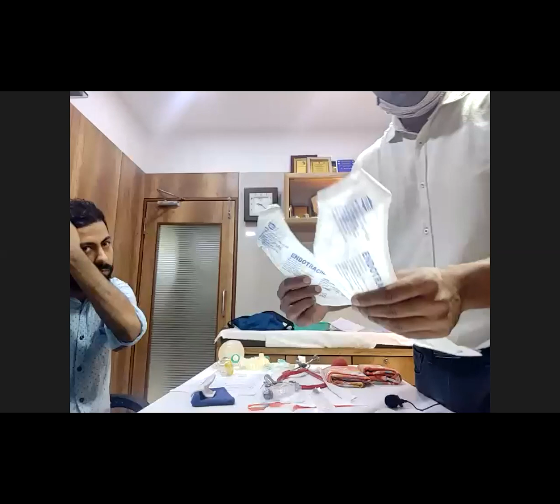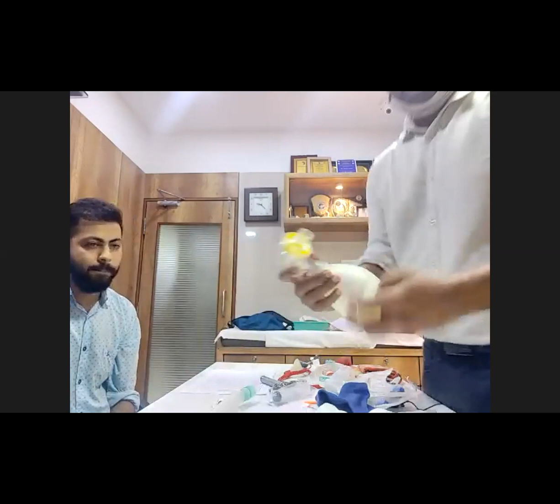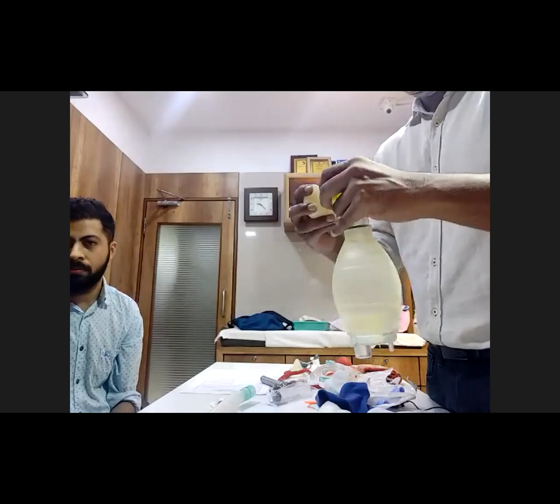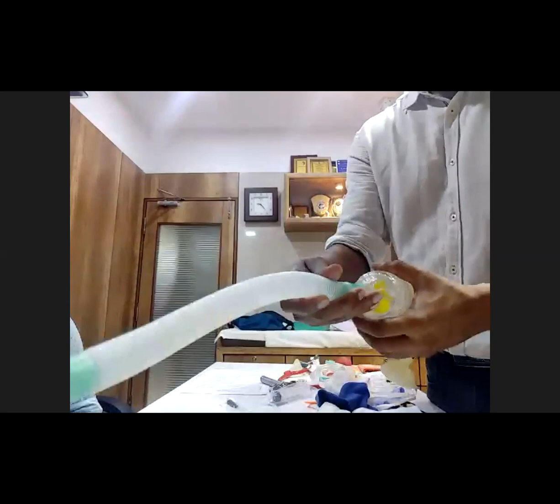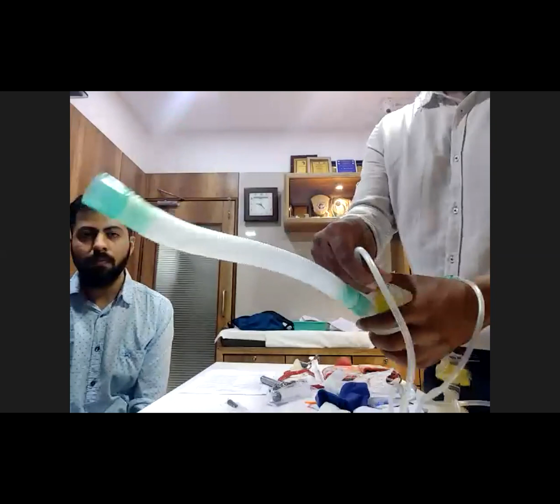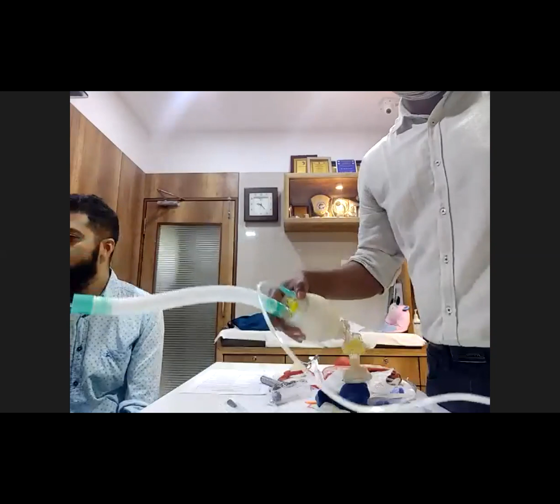So in this, the two important things we have to check are this AMBU and laryngoscope, whether they are working or not. What is the full form of AMBU? Manual breathing unit. Yes. Ambulatory manual breathing unit, self-inflating. So from here we attach the expiratory valve, we attach the mask. How to attach the mask? Anti-clockwise. And here there are two openings, one for the corrugated tube to give 100% oxygen, and one for the oxygen to give, and we have to fix this flow at 8 to 10 liters.